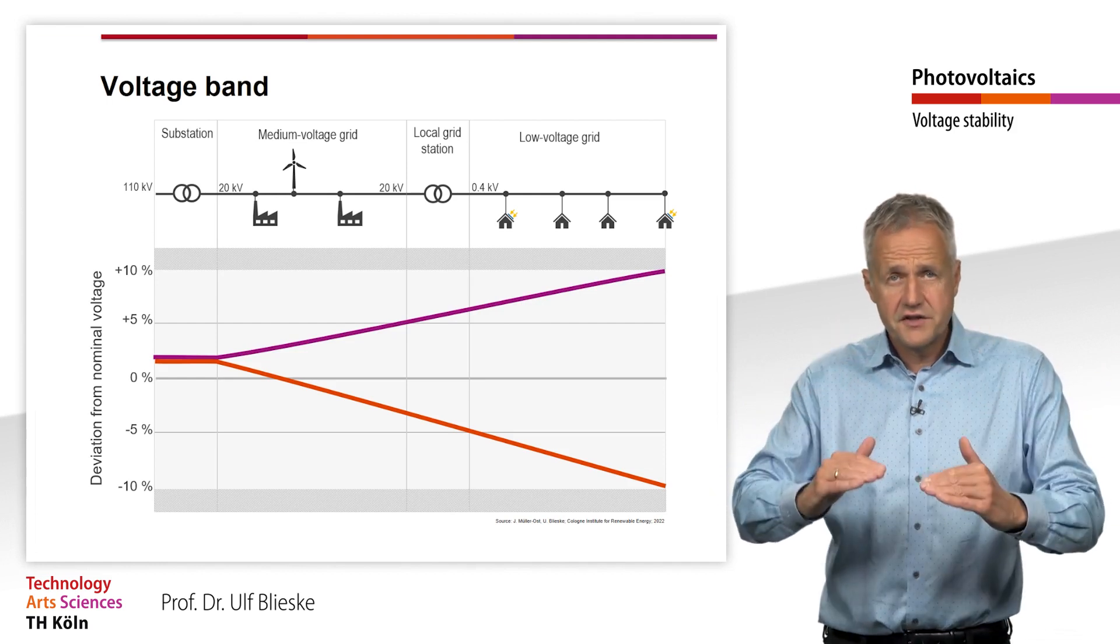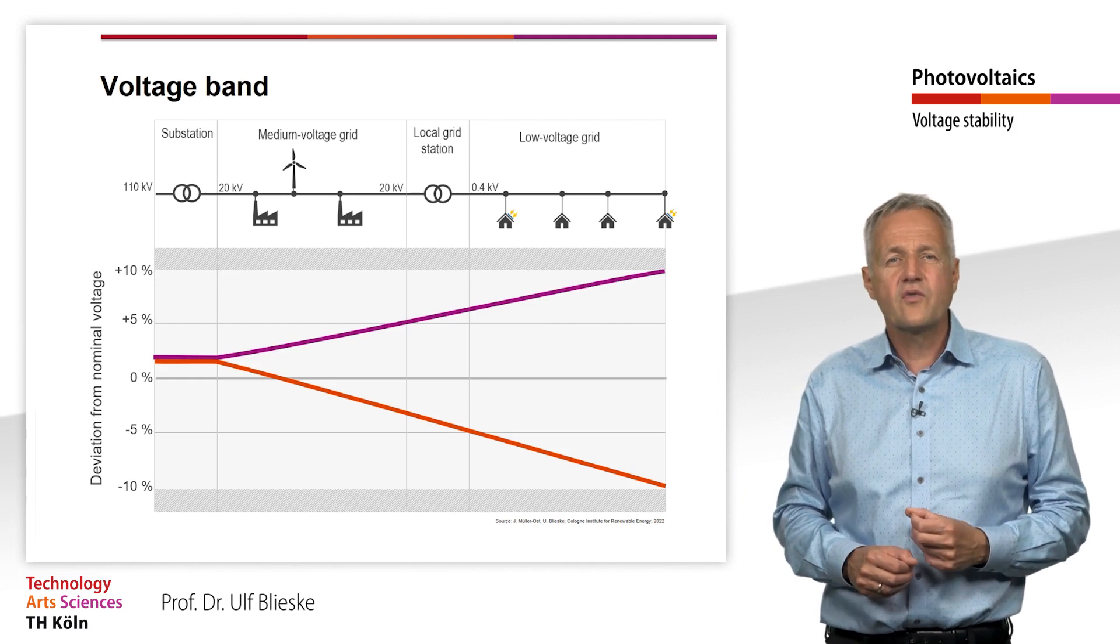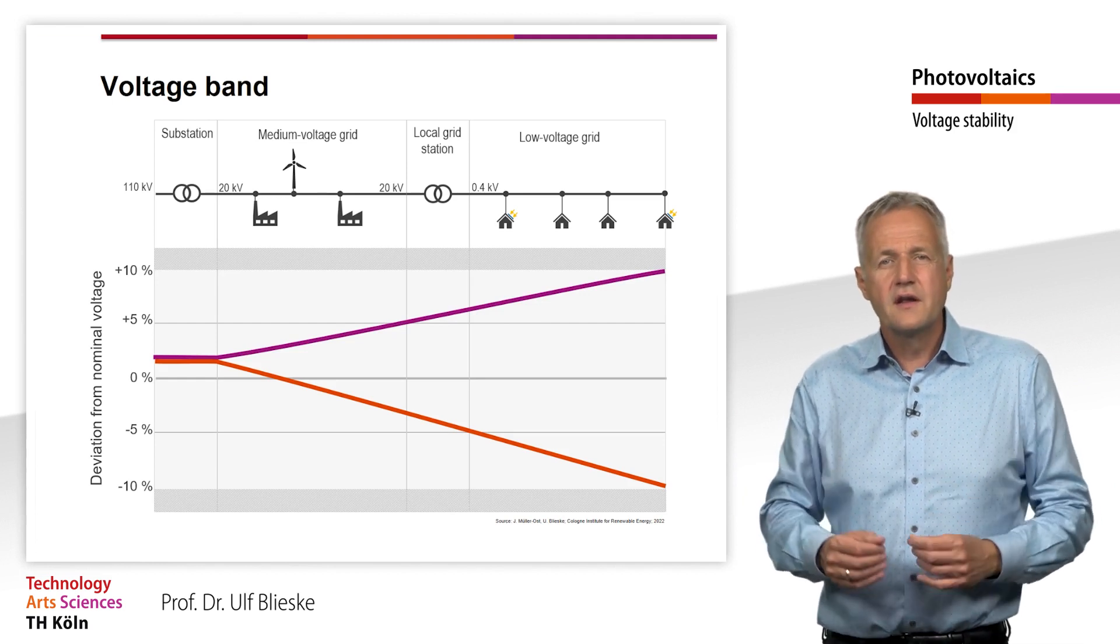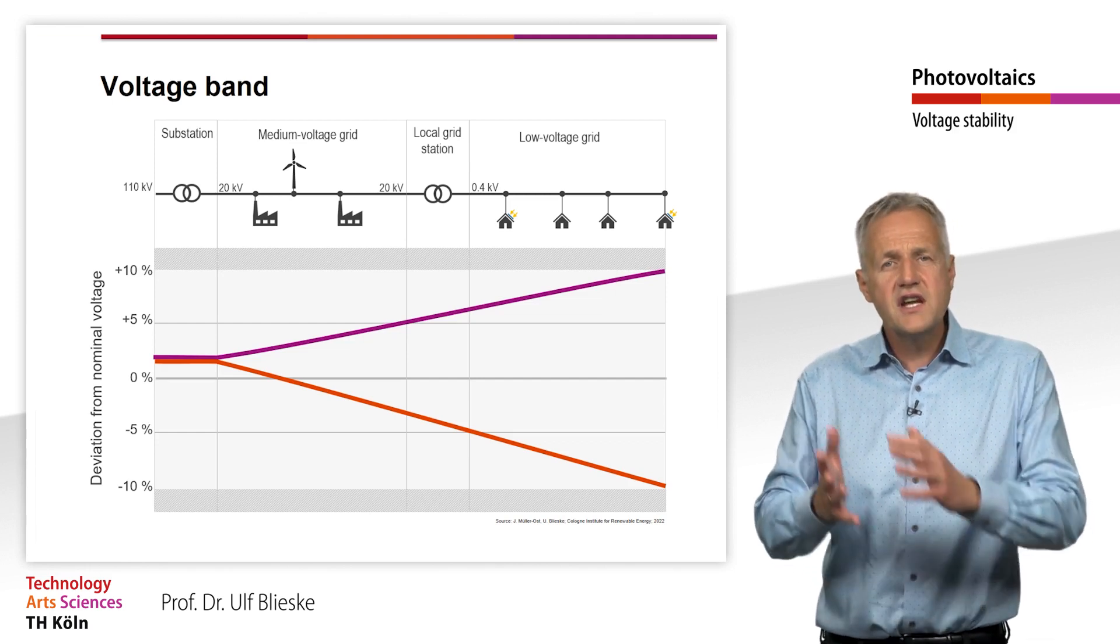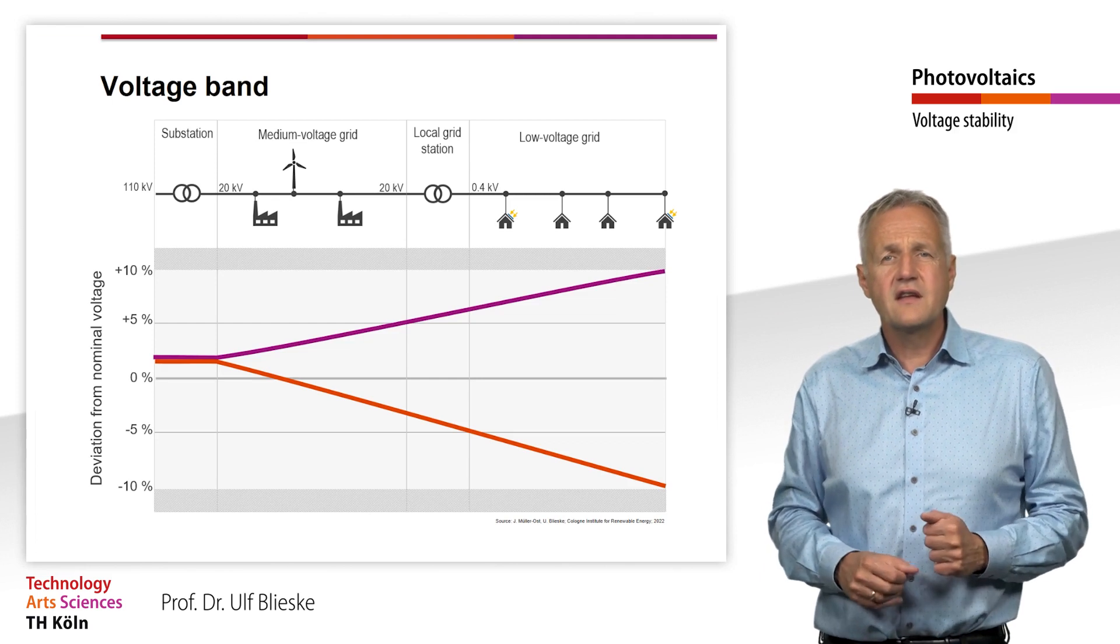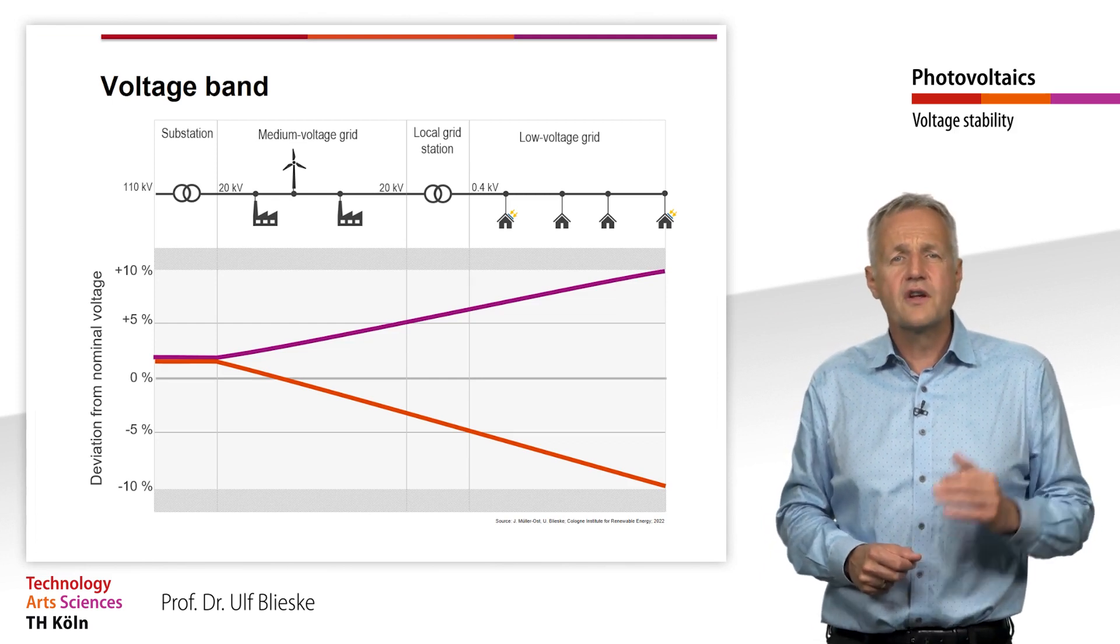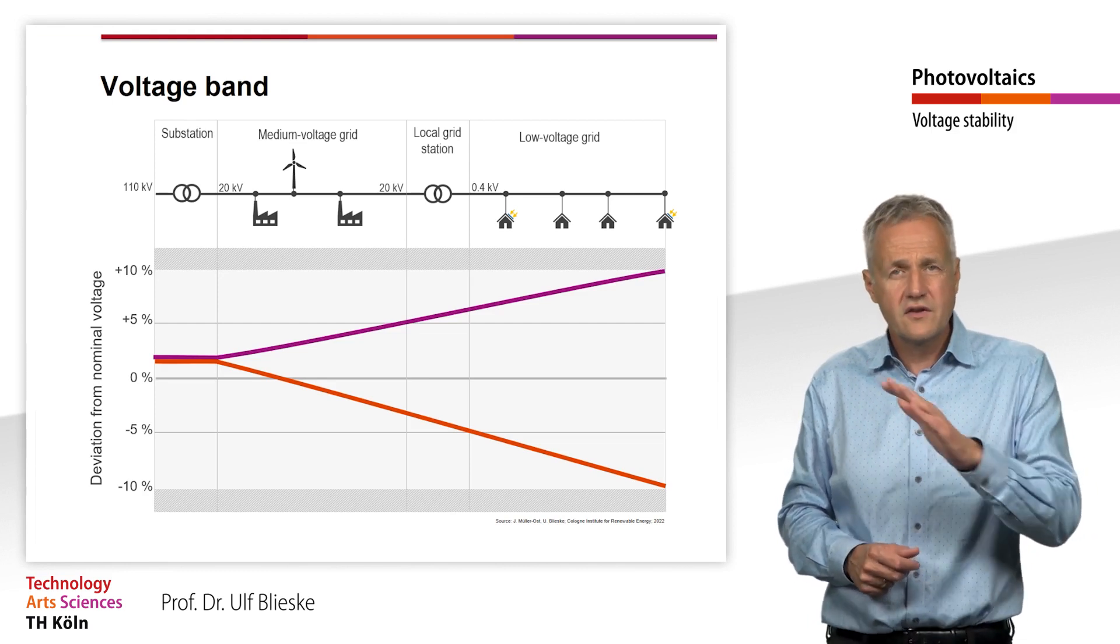Exactly the opposite case occurs when power is not drawn in but fed in. Here, there is a voltage increase at the feed-in point. If the feeding inverter would not set the voltage higher, the current could not flow towards the grid at all.